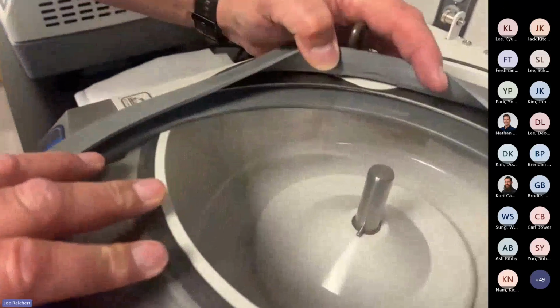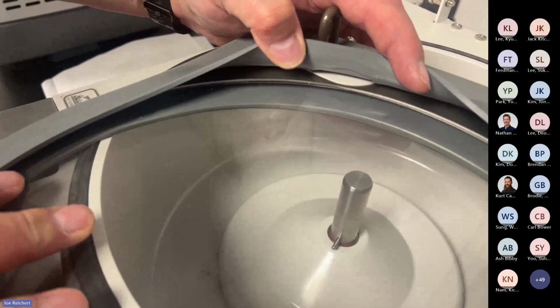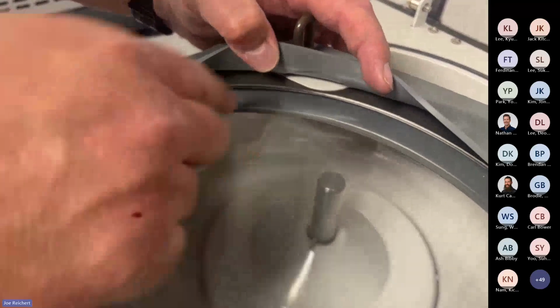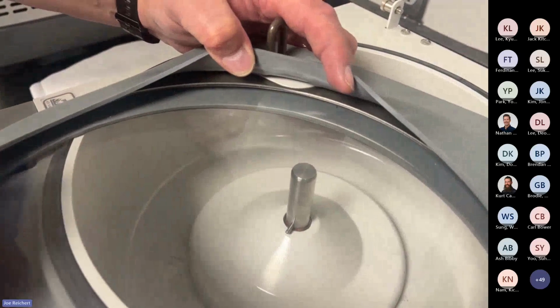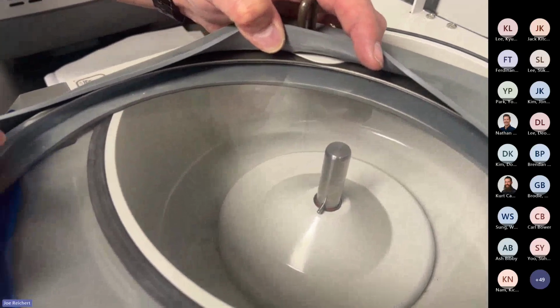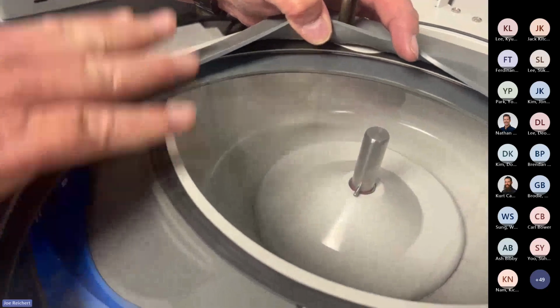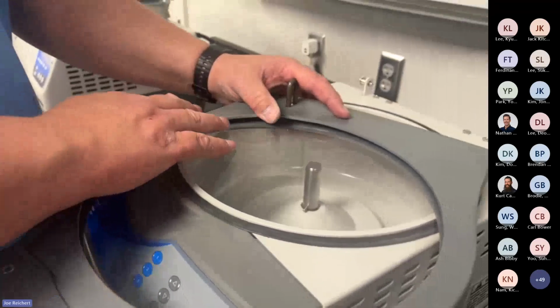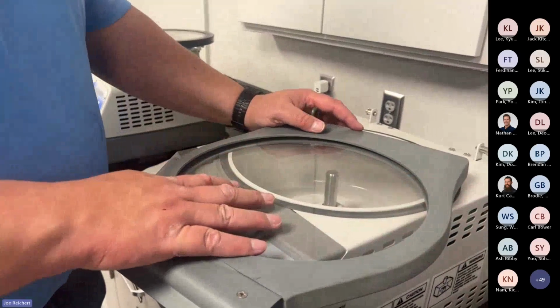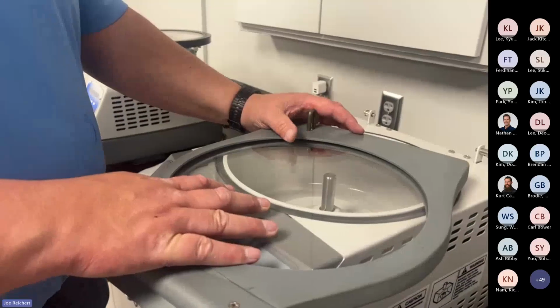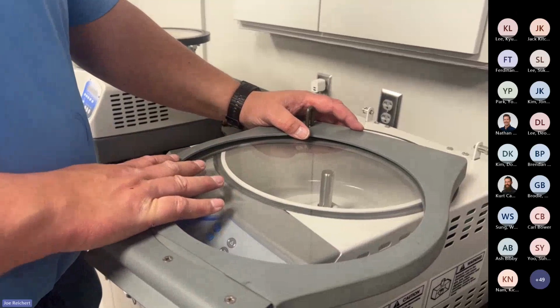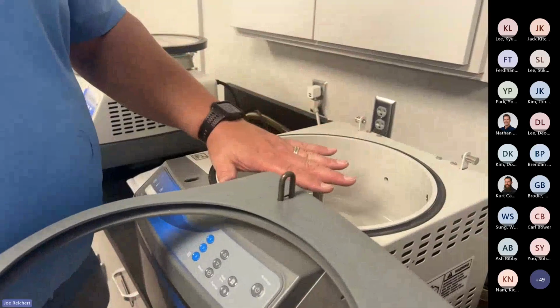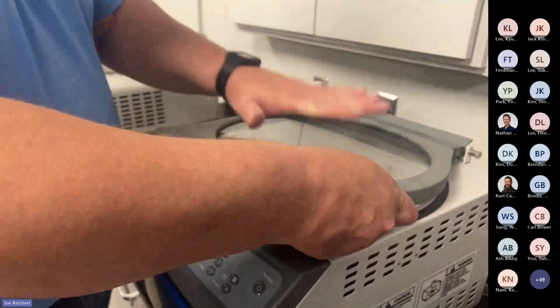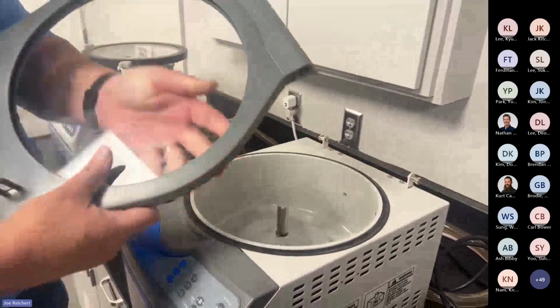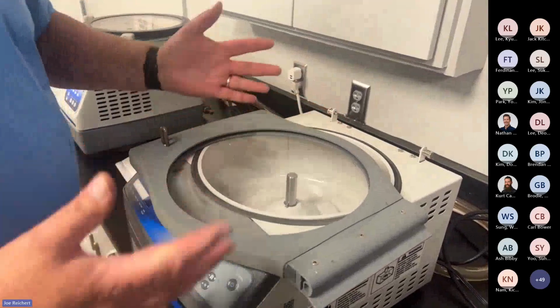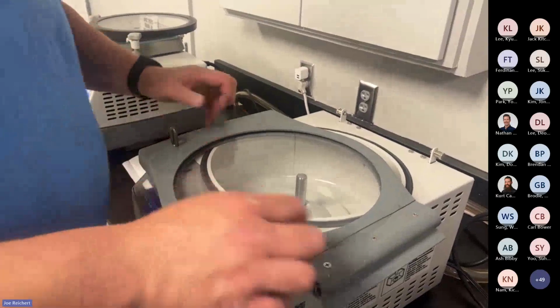And when you get a new CentraVap, sometimes you'll have squealing or squeaking when you first turn on the vacuum pump. It's usually caused because this spacer is metal, and when you cut out metal that thin, it may not be as completely flat as it could be. So it might hold the gasket up a little bit. That squeaking is just the air coming underneath the gaskets. It usually goes away after a few runs, and that spacer will flatten back out on its own. Applying a little hand pressure on top of the lid while it's on the machine, just pushing it down a little bit, will get rid of that squeaking. But it's not a running issue. It's just that the machine needs to be broken in a little bit with that spacer there.